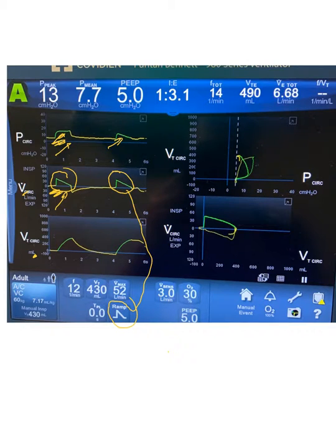So you can tell that this is a flow decelerating ramp target. Because simply, the flow is being the same, that's the target. So the ventilator is keeping its promise by keeping it the way we told it to do it here. And the pressure is variable to keep this target.